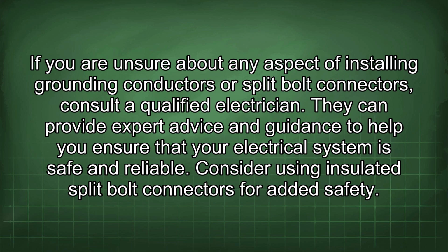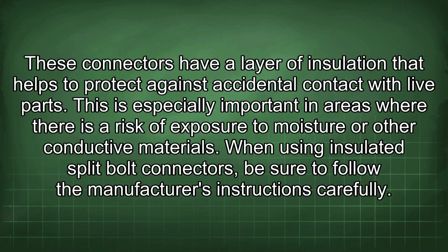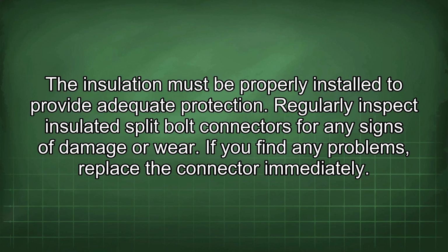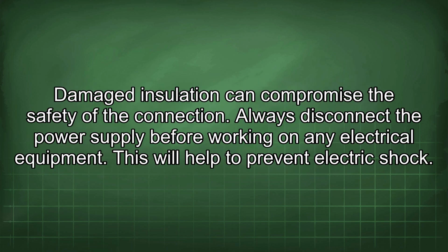Consider using insulated split bolt connectors for added safety. These connectors have a layer of insulation that helps to protect against accidental contact with live parts. This is especially important in areas where there is a risk of exposure to moisture or other conductive materials. When using insulated split bolt connectors, be sure to follow the manufacturer's instructions carefully. The insulation must be properly installed to provide adequate protection. Regularly inspect insulated split bolt connectors for any signs of damage or wear. If you find any problems, replace the connector immediately. Damaged insulation can compromise the safety of the connection.